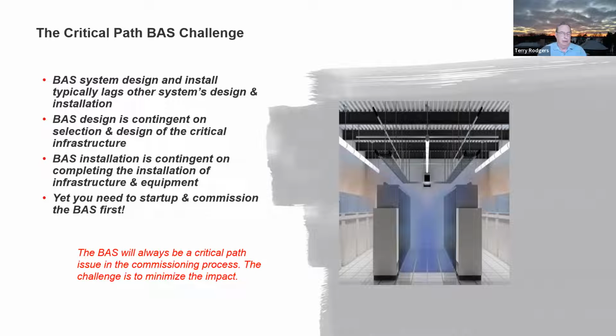And the installation is contingent on completing the infrastructure and equipment installation, because until you have an air handler to land wires on, you can't finish installing the BAS system. And during startup, you can't complete startup of the BAS system until you've started up the equipment it's going to control, it's gone live, been energized, panels are lit up, and it can communicate to and from the BAS system.